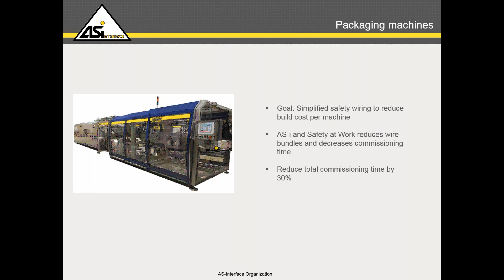Going into this was their typical controls architecture for safety. As most of you know, when dealing with safety components, there's a lot more wiring involved—in many cases 3 times the amount of wiring compared to traditional I/O. In this case, it all goes back to a safety relay, with a couple sets of terminations there, wired to contactors to control the zoning of the machinery. Then there's another separate set of wires for each switch connected back to the PLC for feedback indication. That really increases the amount of labor and complications involved in commissioning the system.